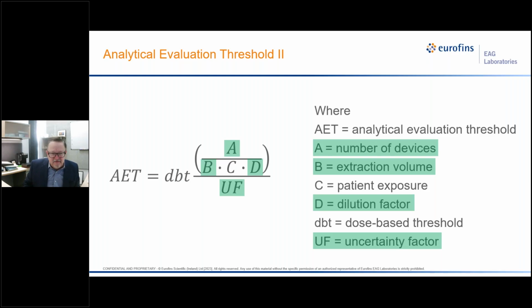Now, that's pretty easy to circumvent if you're doing an exhaustive study, because in an exhaustive study, ultimately, you're going to demonstrate exhaustiveness. And so you're not concerned about saturating the solution because you're going to continue to extract until you can demonstrate that less than 10% of the initial extract is coming out. So you're going to hit the same endpoint. It may take more cycles if you potentially saturated the very first extraction cycle. But generally speaking, you can control B.